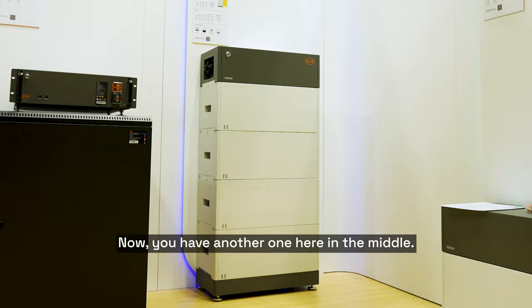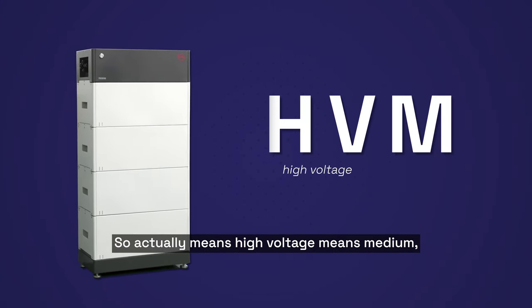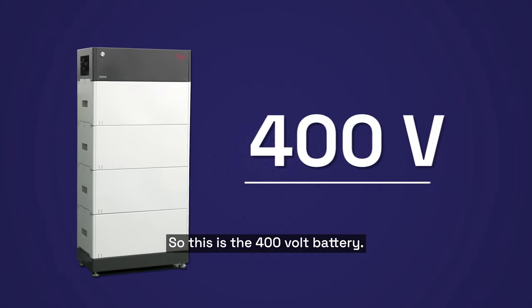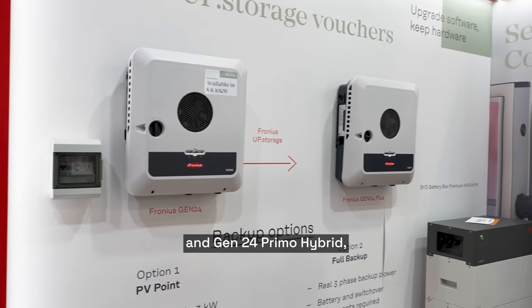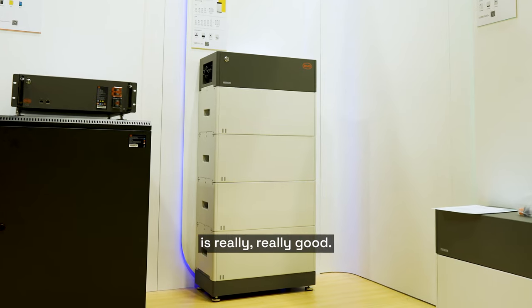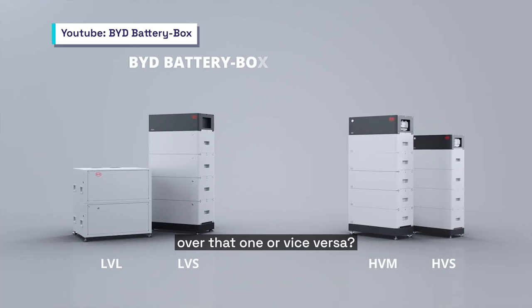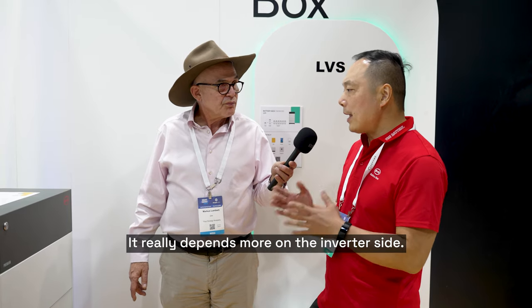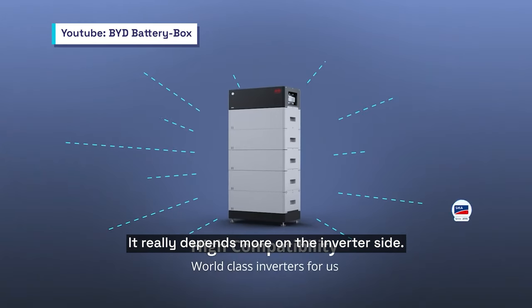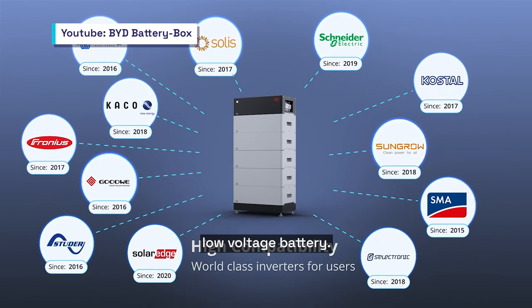You have another one here in the middle — this looks quite sexy. What's the story about this one? HV means high voltage, M means medium. So this is a 400 volt battery. It's compatible with the Fronius, SMA, SunGrow, and Goodwe inverters. The combination of the Fronius Symo Hybrid and Gen24 Primo Hybrid with this BYD HVM is really, really good. Why would somebody choose this one over the other? It really depends on the inverter side — high voltage inverter, go with high voltage battery; low voltage inverter, low voltage battery.